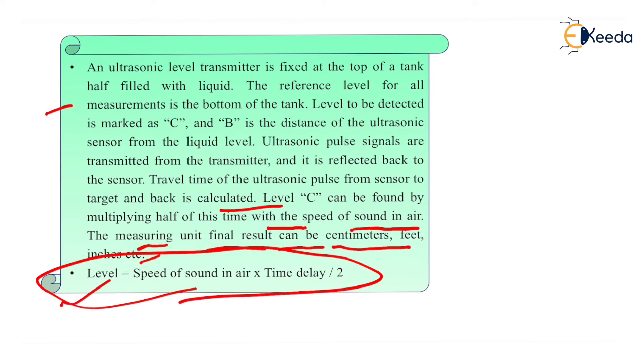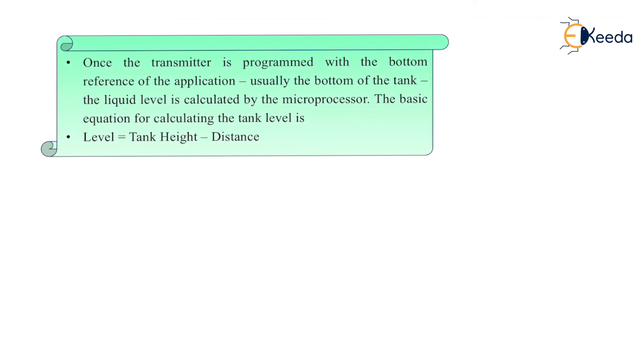The ultrasonic pulse signals are transmitted from the transmitter and reflected back to the sensor. The travel time is measured and used to calculate the level of the liquid. Once the transmitter is programmed with the bottom reference — usually the bottom of the tank — the liquid level is calculated by the microprocessor using the basic equation: tank level = tank height minus distance.